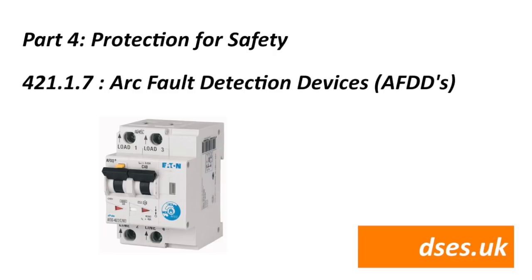At present a house may pass a test and inspect as part of a new CU change, but I cannot absolutely guarantee any given home is completely free from loose connections. If I install an AFDD board onto older wiring and it keeps tripping because of a loose connection in a junction box under the floor that's been there for 25 years, what chance have I got? It's fine on new builds where you know the circuit routes, but older properties could be a nightmare. Even on new builds, if you turn up and find it tripped, you need to know whether it was an overload, earth fault or arc fault. I'm not convinced — but the Yanks, Aussies and Germans use them, so there must be something in it.